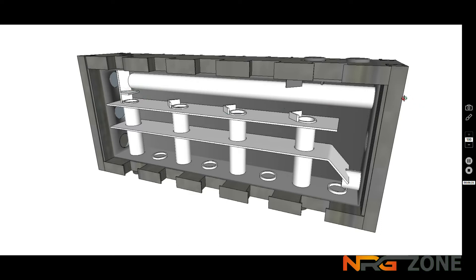If we take the front cover off, you see that the energy zone unit is divided into three areas. If a boiler delivers a flow in from the right hand side at R1, being the top right hand connection, or L1, being the top left hand connection, that water will start at this point and move, passing each of the zone opportunities here, to go back to wherever it came from, back to the boiler. So the boiler's only job is to push water through this, which acts perfectly as a low loss header, as well as a zoning device, and many other features you'll see.